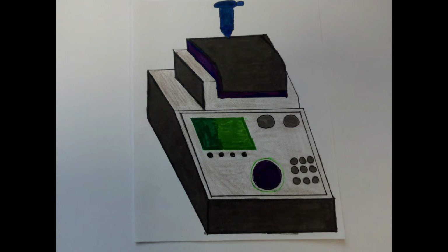The machine. A thermal cycler, also known as a polymerase chain reaction machine or thermal PCR cycler, is a device used in molecular biology that allows performing the temperature cycles necessary for a DNA amplification polymerase chain reaction or for sequence reactions with the Sanger method.